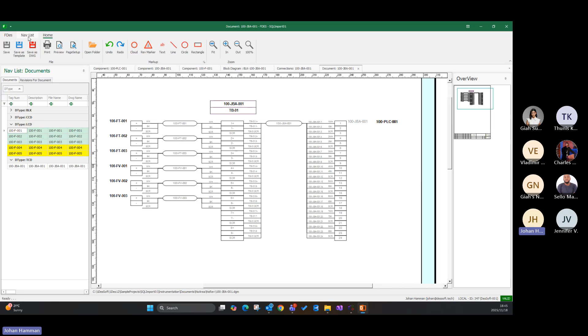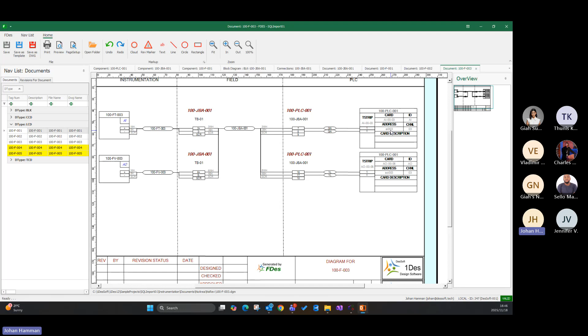If I look at my loop drawings, I can see there's 3 loops, and I can just update and view them, and it will create those 3 loop drawings from the data. So now you will see there's my 3 loops, flow transmitter 3 and valve 3, how it's connected to this JB, to a landing strip, my analog input card. I can see the software addresses, the channel, the terminal numbers, and then for the second one, it's different numbers, different channel, and so on, green, yellow. And there you can see how quickly it is to get to this level for the 3 loops.